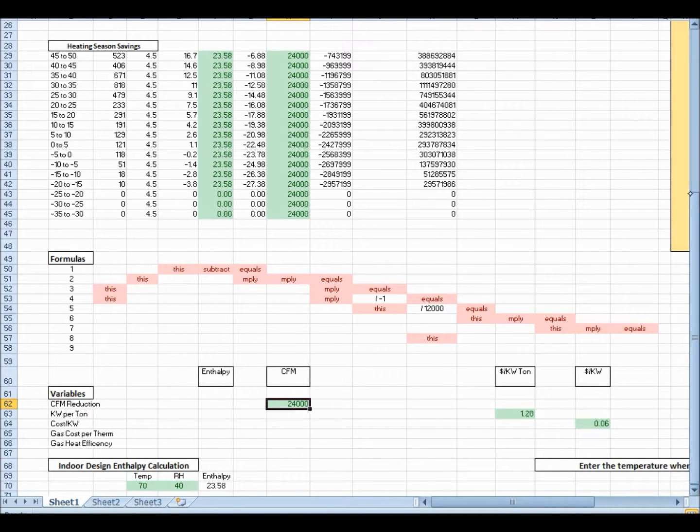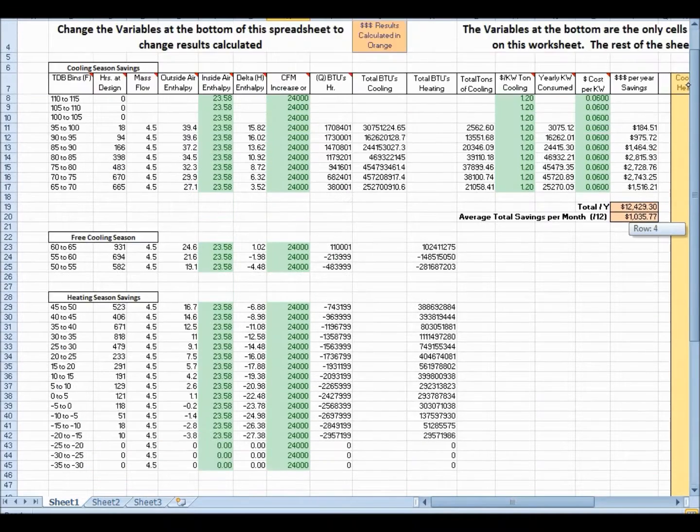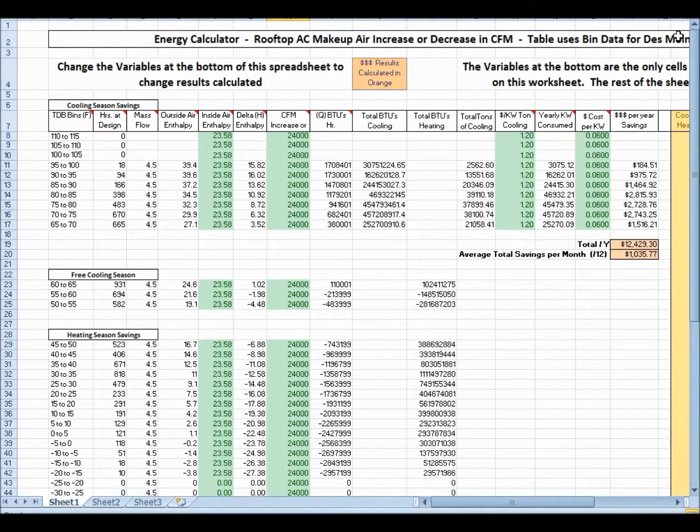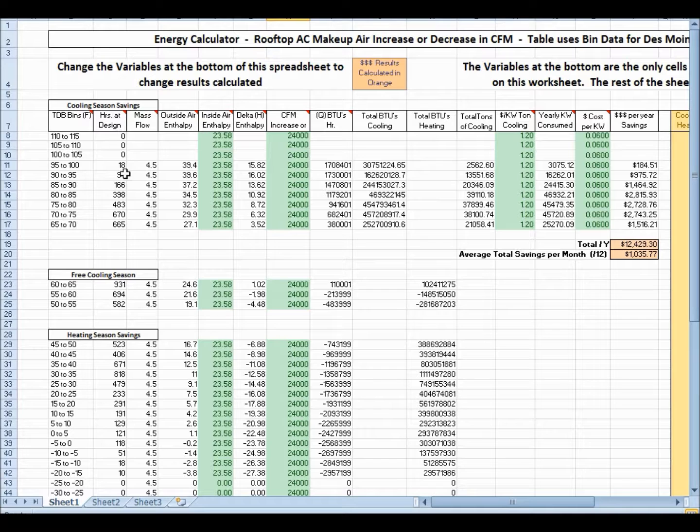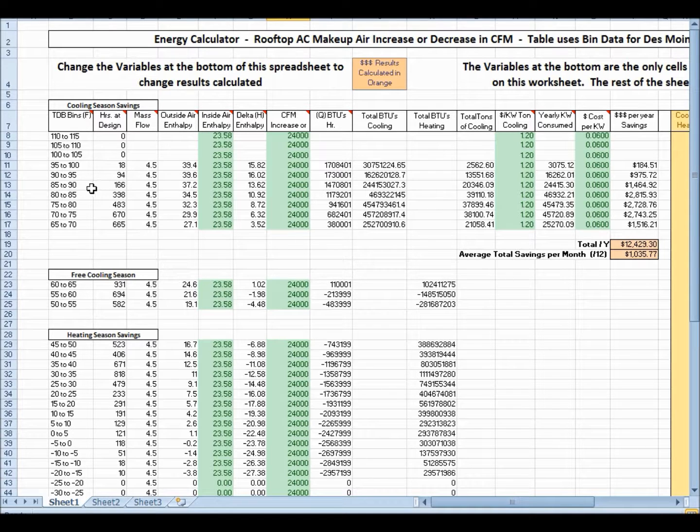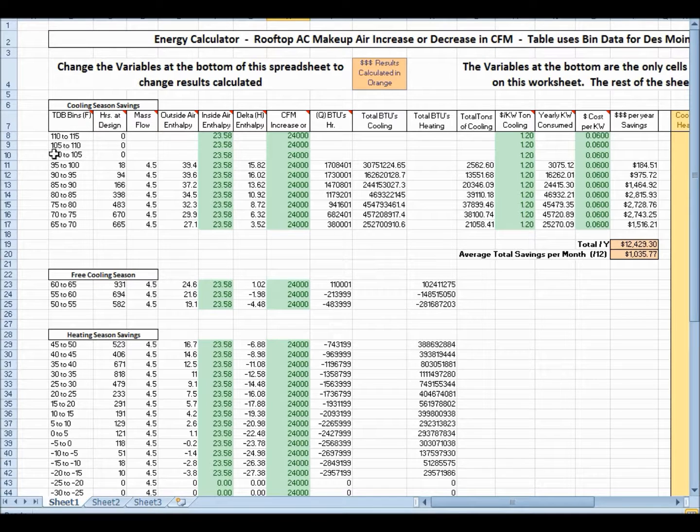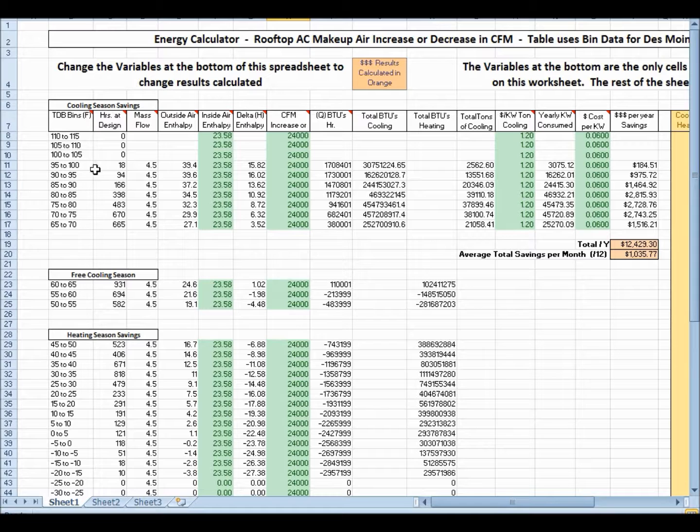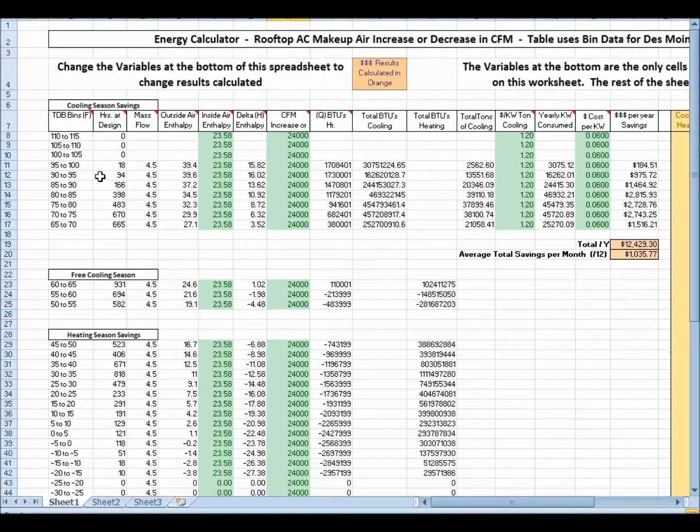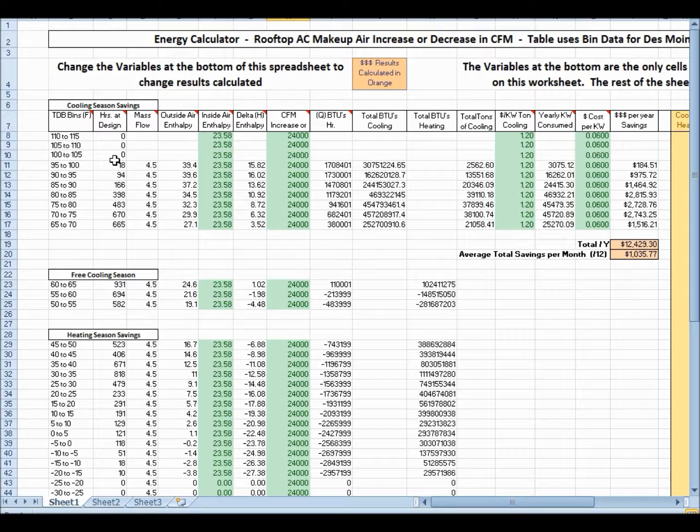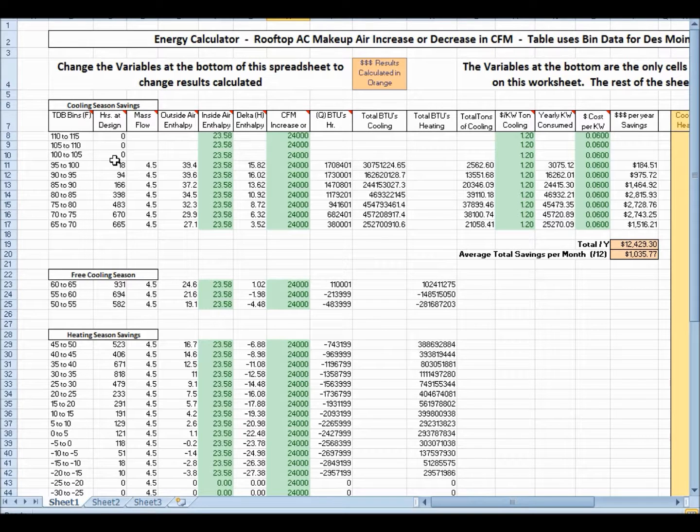Other cities do, like Minneapolis or Alaska. And then the same is up here. You can see that there isn't any design hours for bin data. Again, this is Des Moines, Iowa. We've got zero, zero, zero on 100 through 105, and the first one is 95 through 100. There are 18 hours per year that it's at that type of design condition.